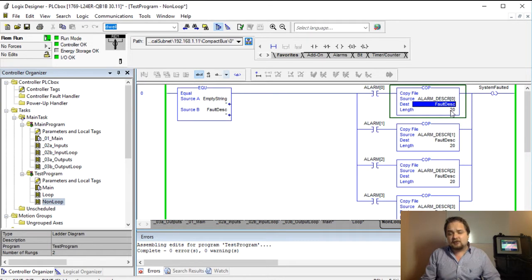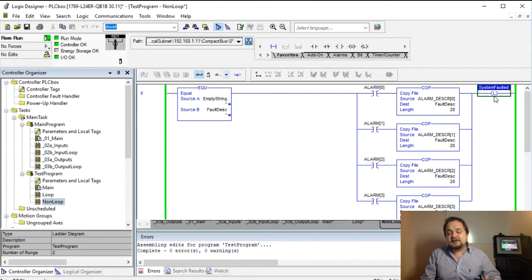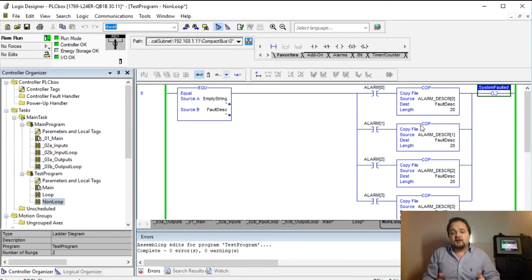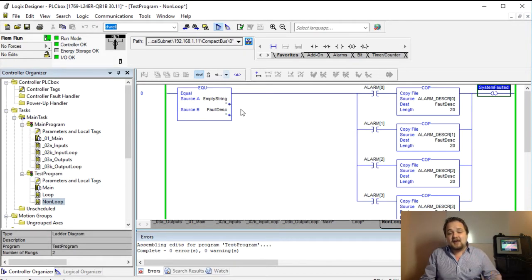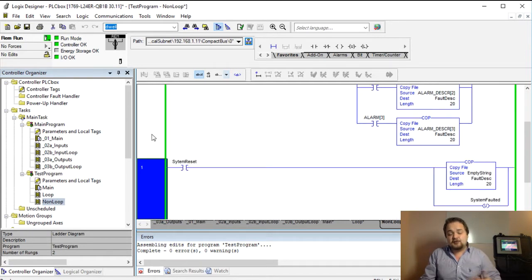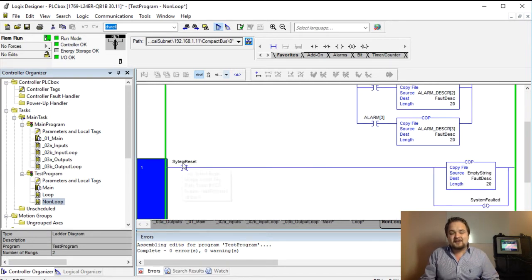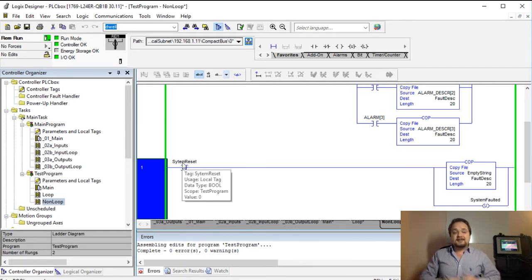And that's going to be 20 characters and you're essentially latching in a bit which is going to be a system fault bit at the end of that operation because you are indeed faulted and since the string is no longer going to be empty, I had to latch in this bit and I'm going to show you where that's unlatched which is in the next rung. So if a system reset, so think of this just a push button on your HMI or just on your system in general.